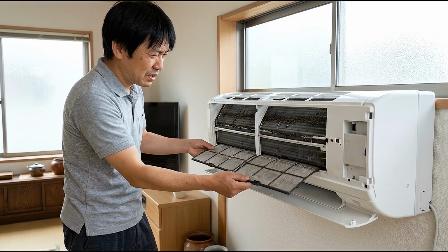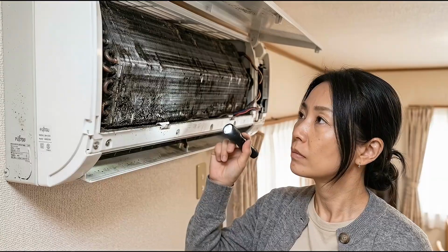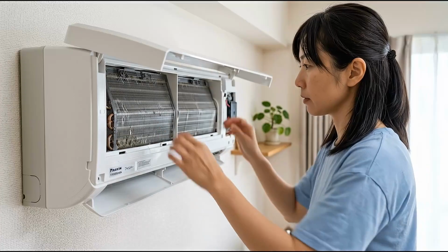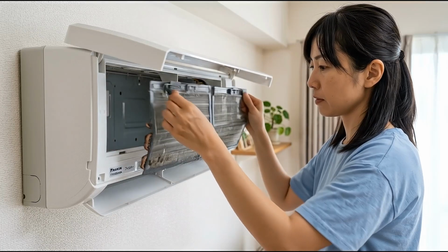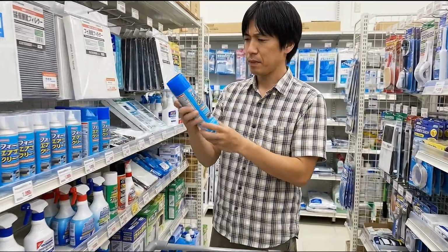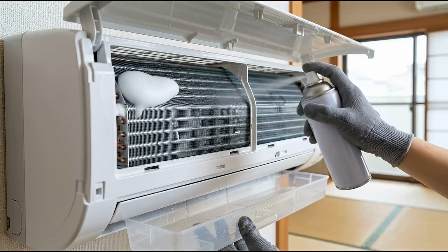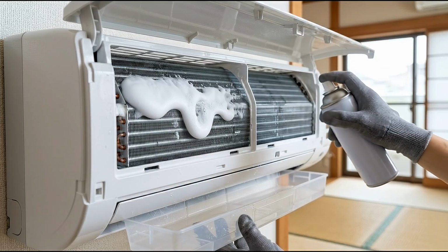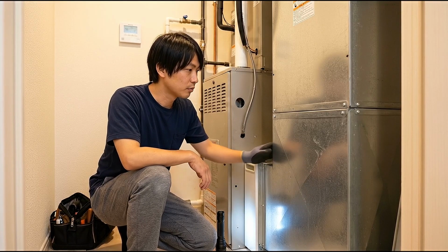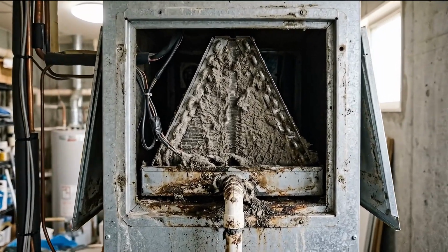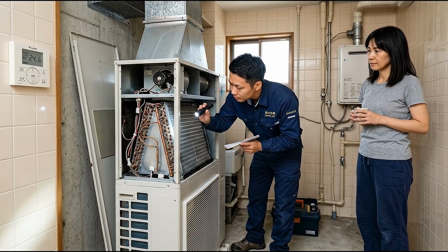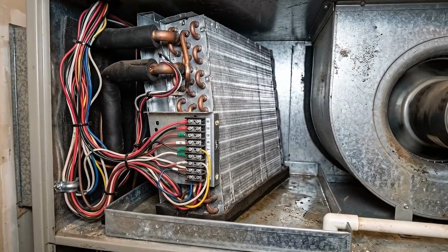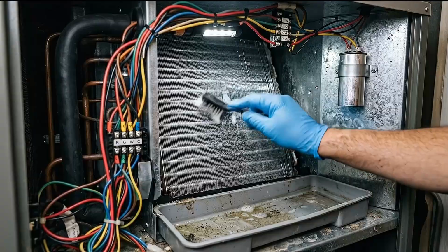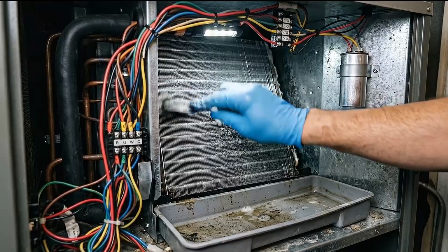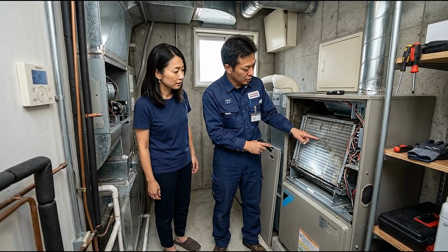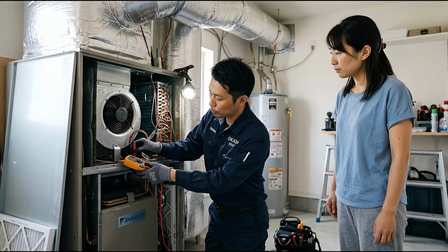If the evaporator coil is already visibly dirty, or if your system smells musty when it kicks on, the coil needs cleaning. On a mini-split, you can access it by popping the front panel and lifting out the filters. Foam no-rinse coil cleaners, available at any hardware store for around $8 to $12, spray on and drip off into the drain pan. On a central air system, you may be able to access the coil through the plenum access panel. But if the buildup is heavy, this is where a professional cleaning makes sense. The evaporator coil is close to the blower motor, the drain pan, and electrical connections, and a wrong move with cleaning solution can cause problems. Professional evaporator coil cleaning typically runs $100 to $400 as part of a maintenance visit.